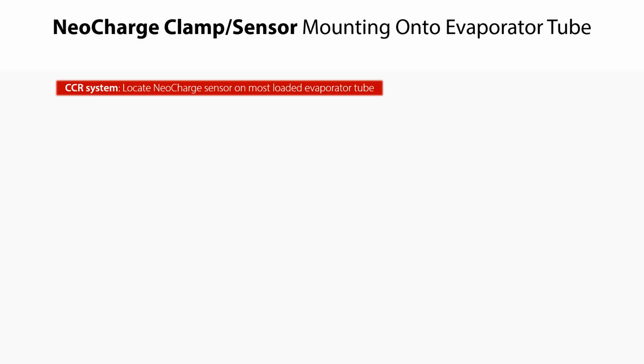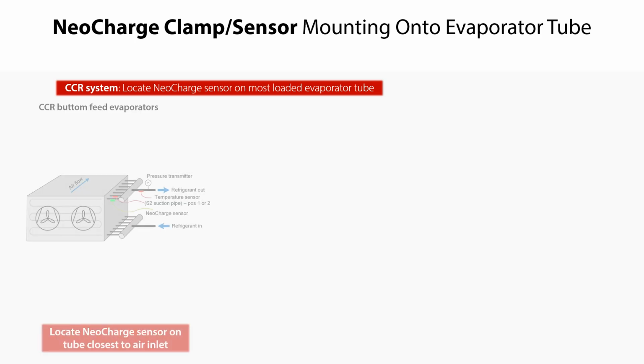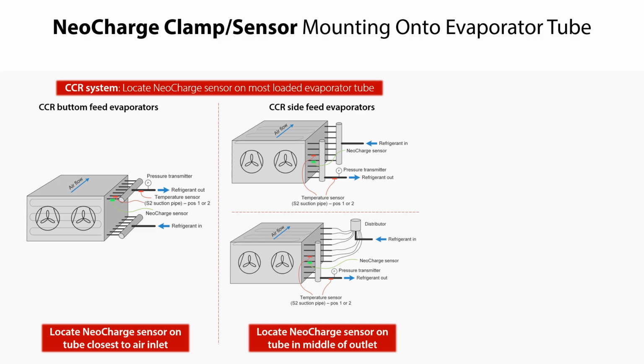The location of the Neocharge sensor on the evaporator tube depends on the type of evaporator system. For a CCR evaporator system, the Neocharge sensor should be located on the most loaded evaporator tube, meaning the tube with most gas in the outlet. This will give the most liquid in the evaporator outlet. This means that for a CCR bottom feed evaporator, the sensor should be located on the tube closest to the air inlet as shown here. And for a CCR side feed evaporator without or with a distributor, the sensor should be located on the tube in the middle of the outlet as shown here.